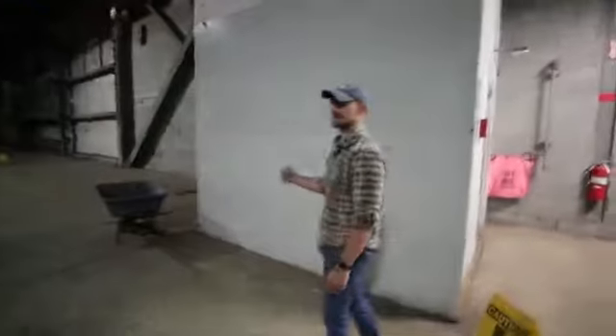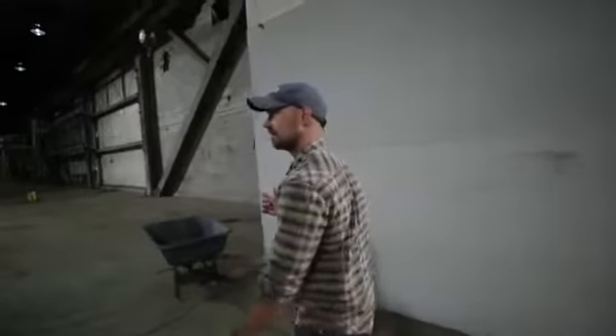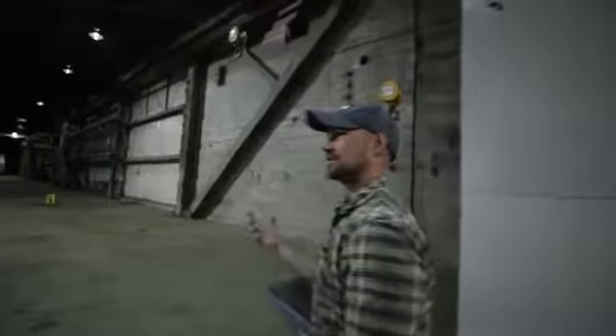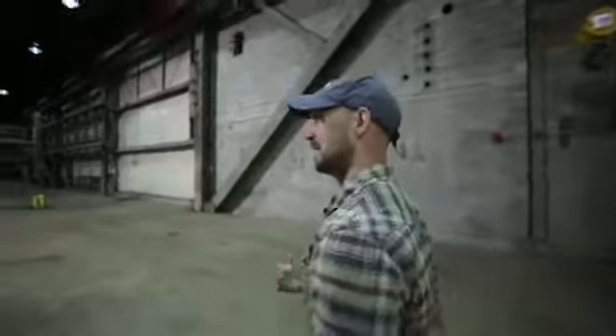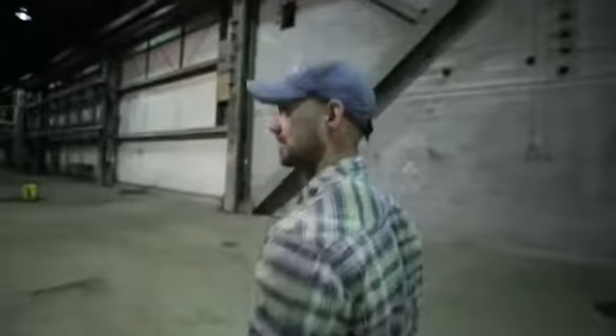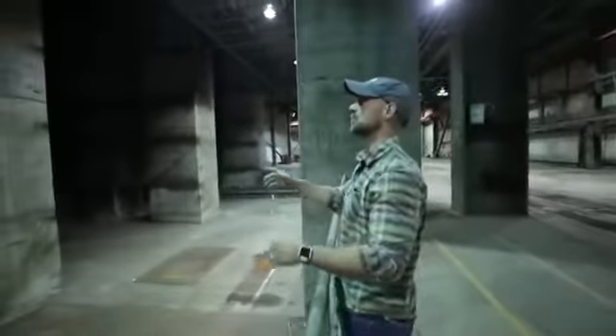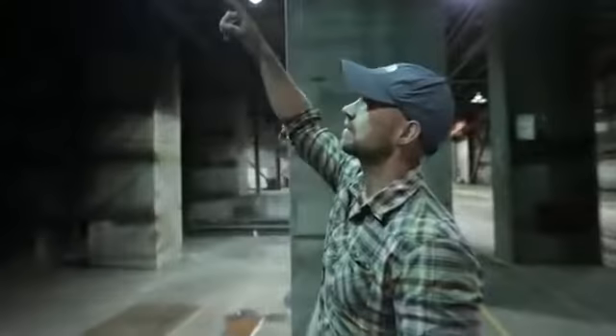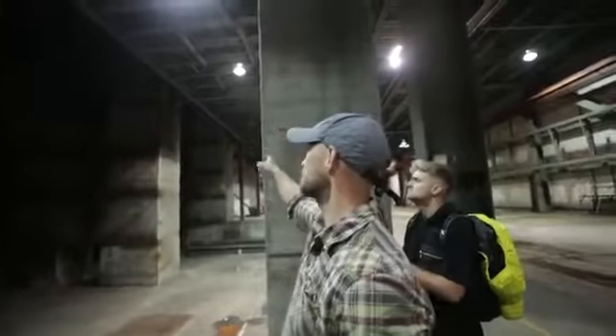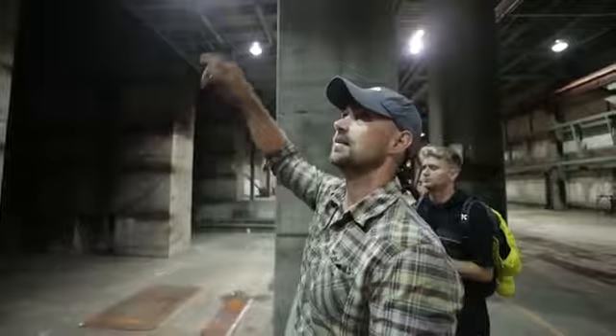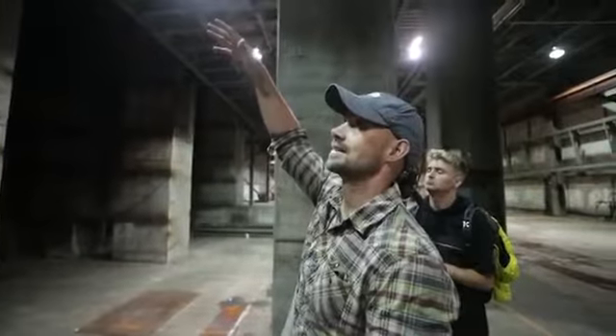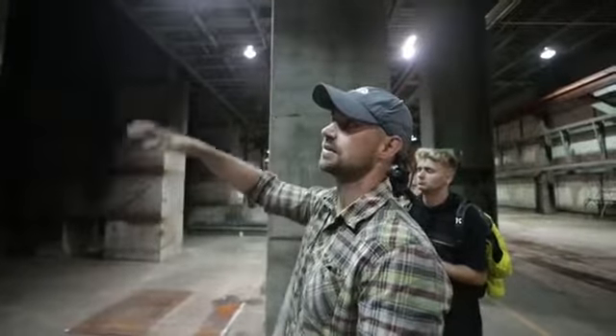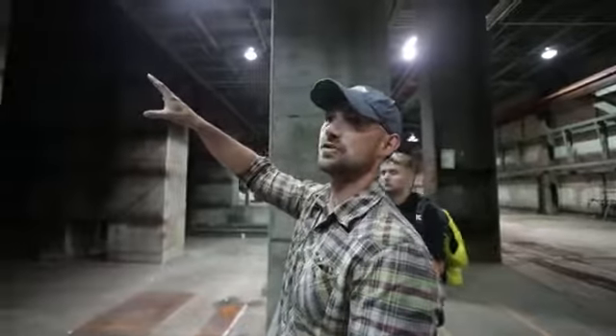We'll walk you through where the condensers were so you can get an idea where the water condensing from the turbines met the 12-foot diameter piping back to the cooling tower. Imagine this large square area is one condenser, and on top of it was one turbine. There's a high pressure turbine and 3 low pressure turbines, each with a condenser. The steam going through that turbine condenses back into water through this condenser, which has about 188,000 1-inch tubes inside.